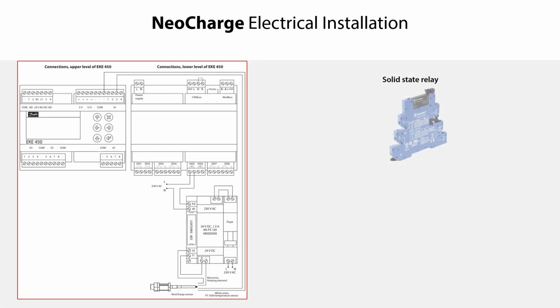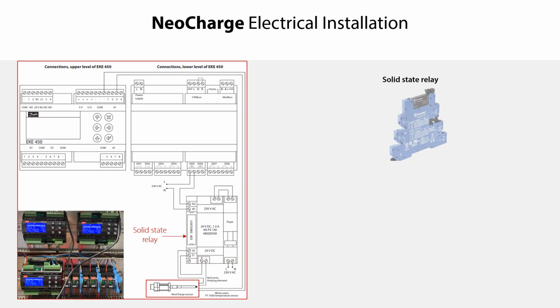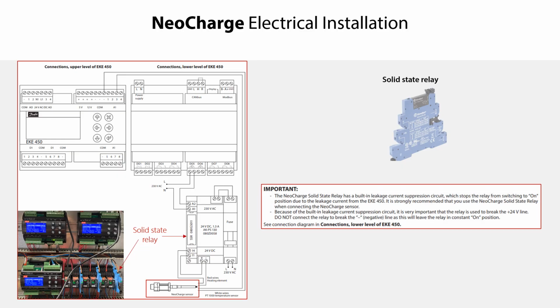Here you see a diagram which shows how to electrically wire and connect the Neocharge sensor together with the solid-state relay and the EKE 450 controller. You also see here a photo with an example of how the solid-state relay is located and wired to the controller. In this example, there are 3 solid-state relays and controllers for 3 evaporators. The solid-state relay has a built-in leakage current suppression circuit which stops the relay from switching to on position due to the leakage current from the EKE 450. As specified, we strongly recommend that you use the solid-state relay when connecting the Neocharge sensor to the EKE 450 controller. Because of the built-in leakage current suppression circuit, it is very important that the relay is used to break the plus 24 volt line.